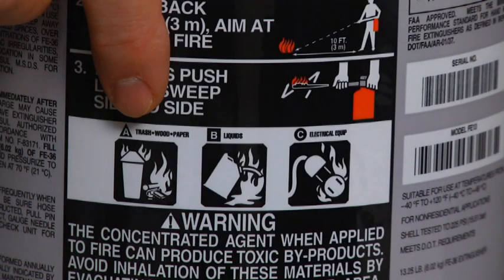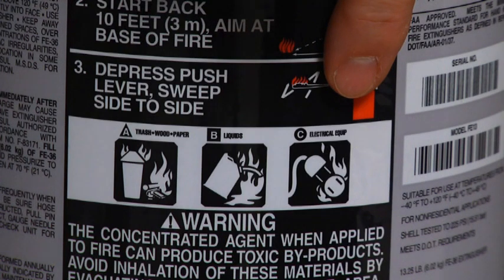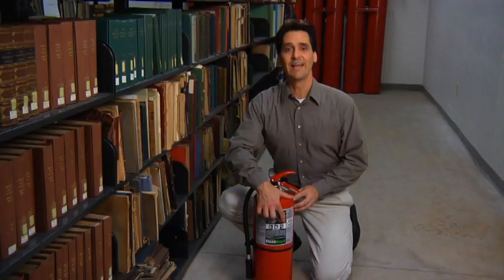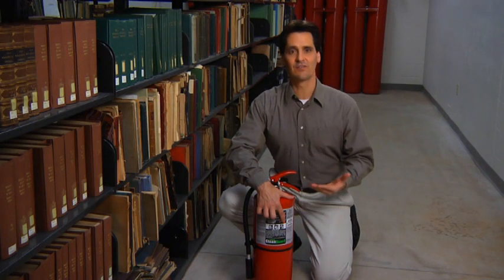Class A means that this Ansul extinguisher is rated for most ordinary combustibles like wood, paper, and cloth, while Class B means that it can be used for flammable liquids and gases. Class C indicates that this extinguisher is rated for energized electrical hazards involved in a fire where the agent inside is a non-conductor of electricity.